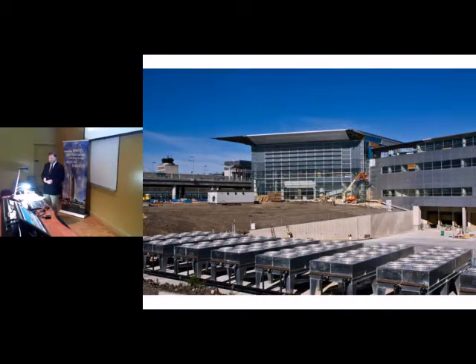One other system that I won't get into great detail about, but we do also use a condenser water loop inside the building that recycles heat within the building. So any area where there's, say, a computer room, a store that needs air conditioning all year round, a restaurant, that kind of thing, we have water-to-air heat pumps in those spaces. So we extract whatever energy is in that space, whatever heat they don't need, compress it and put it onto a condenser water loop. So basically there's a loop of water that just pumps water around the building. We inject energy into that loop, and then other devices in the building where they might need heat are able to extract that energy and reuse it somewhere else. So it's basically an ability to move heat from one spot in the building to another spot using this loop.